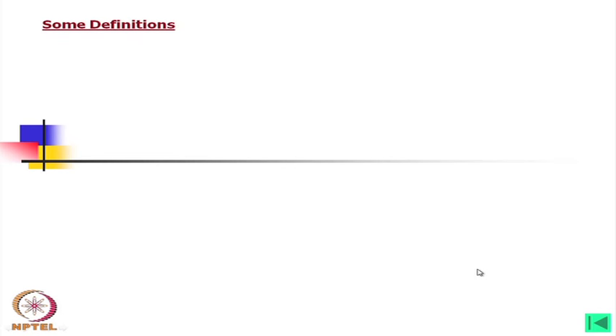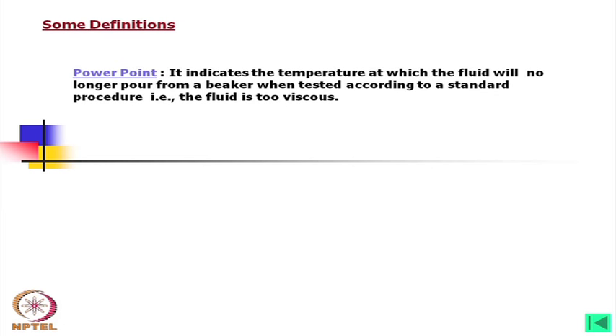Along with that we must know some definitions and terminology. There is a spelling mistake here — it is not 'power point' but 'pour point,' P-O-U-R. Pour point indicates the temperature at which the fluid will no longer pour from a beaker when tested according to a standard procedure. This means the fluid is too viscous, and this test is conducted particularly at low temperatures.